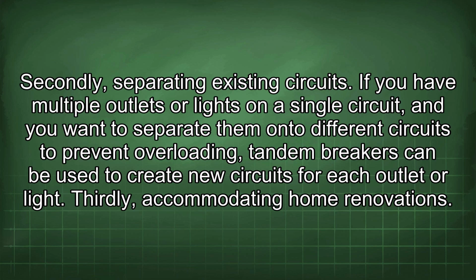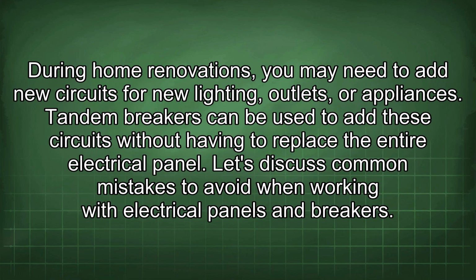Secondly, separating existing circuits. If you have multiple outlets or lights on a single circuit, and you want to separate them onto different circuits to prevent overloading, tandem breakers can be used to create new circuits for each outlet or light. Thirdly, accommodating home renovations. During home renovations, you may need to add new circuits for new lighting, outlets, or appliances. Tandem breakers can be used to add these circuits without having to replace the entire electrical panel.